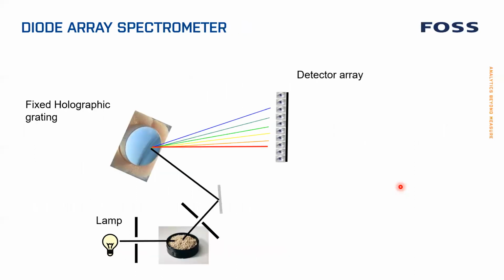Then the last one is the diode array. This is what we call a post-dispersive, which means it's dispersing the light after it hit the sample. So you have a lamp with all the different wavelengths hitting the sample. The reflected light, or could be the transmitted light, goes through, hits a grating, and the grating is fixed. It's not moving as it is in the monochromators. And then the light is split up, and there's an array of detectors, typically 256 detectors in an array here.